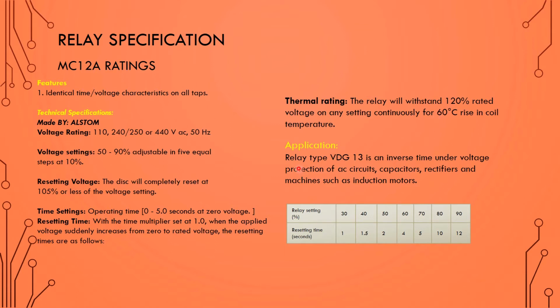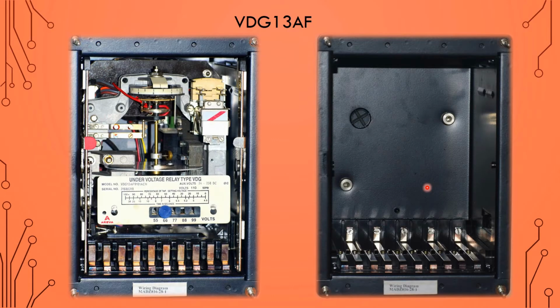And the application, if you see, is in the protection of AC circuits, capacitors, rectifiers, and machines such as induction motors, etc. Then this is the relay diagram, front view. As I showed you, this is flush mounted, so you can remove the relay from the box. The same over voltage relay was also flush mounted, and the electromechanical overcurrent relay was also flush mounted.